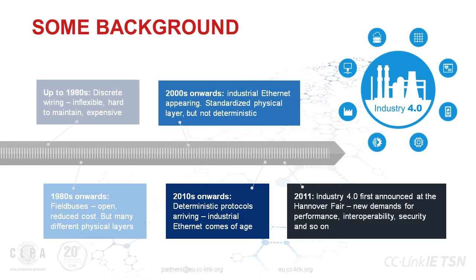Starting around the 2000s, we saw the introduction of industrial Ethernet. The benefit was that you now had a standardized physical layer, giving a more standardized way of connecting things. But we still had some drawbacks — the performance of these networks was generally not deterministic, so you never really knew when something was going to happen. Around the 2010s, deterministic protocols started to be introduced, such as CC-Link IE, PROFINET, and others, which put a deterministic layer on top of Ethernet. At this point, Ethernet really started to get going in automation, because we now had pretty much everything we needed.